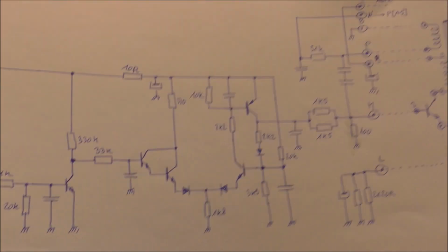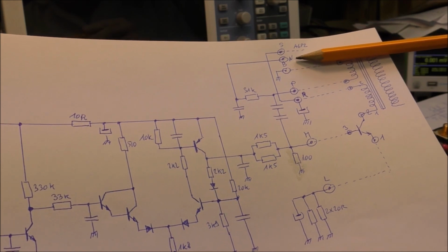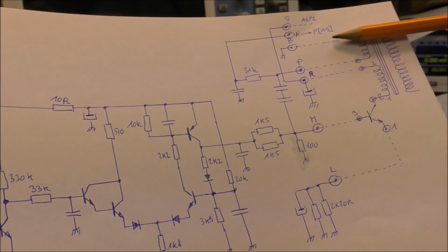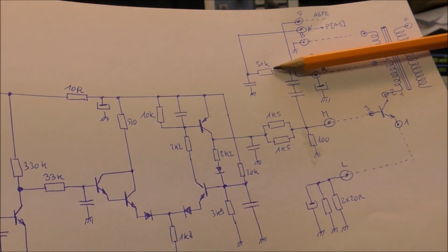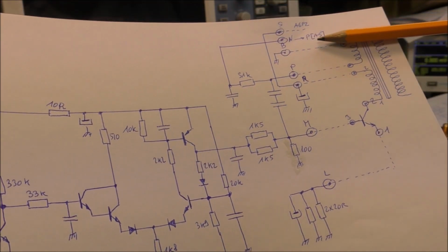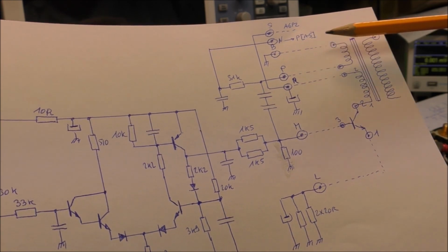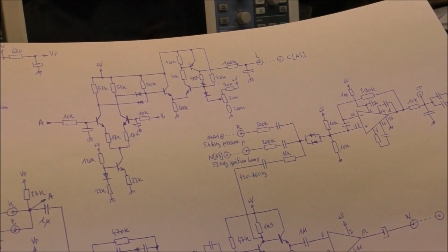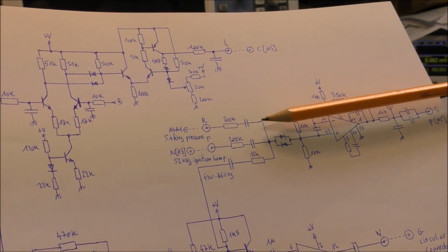We can see also on this generator that there is a signal here on pin N, which is actually the signal of the feedback winding. It is a little bit filtered using this resistor and this capacitor, and this is fed to another circuit, which is the summing amplifier. It is on that page. So this is the preamplifier which permits to have the sum of three signals.